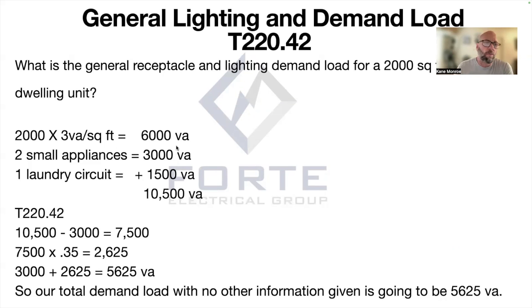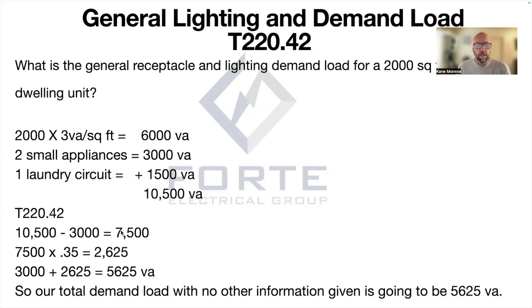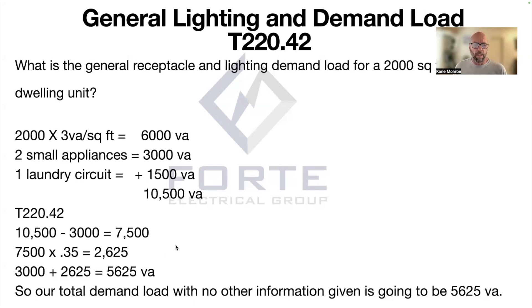Going back to our demand factor: we take 10,500 and subtract 3,000 from that because we apply 100 percent to the first 3,000, leaving a remainder of 7,500. We then take that 7,500 and multiply it by 0.35 — that's your 35 percent from the table — giving us 2,625. We then add the 3,000 back in, and our total demand load is 5,625 VA.